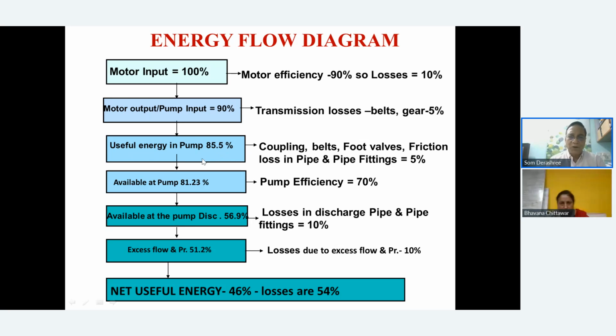About 5% if you knock off, then you get about 81 at the pump, and then pump efficiency is 70%. So you get equivalent hydraulic energy of only 56%. Then there are losses in the discharge pipe and the pipe fittings, etc. Let's say you consider it is about 10%, then you get the efficiency or actual output.